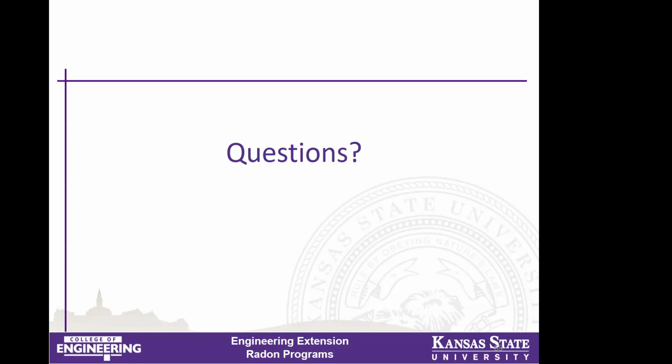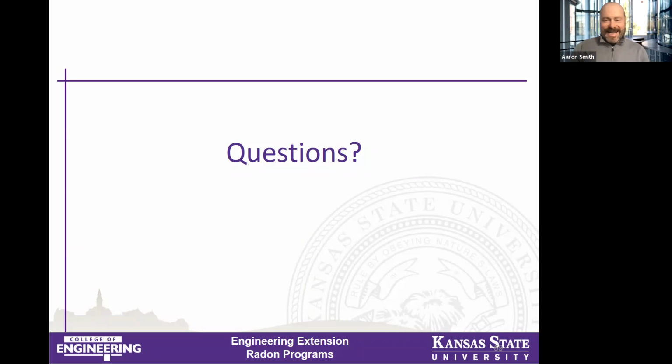I think the answer to that question is no, an ERV does not substitute for a conventional radon mitigation system, or at least a minimum passive system right now in radon zone 1 homes. With that said, I think there are potentially some radon mitigators who do retrofits in homes that might recommend ERVs in some situations to mitigate. Bruce and Brian might know better, but it's not the conventional way that we want to do it. We want to get that radon, the soil gas, out of the home before it gets into the home. Right. That is kind of the intent here. Yeah, you want to isolate it and mitigate it.